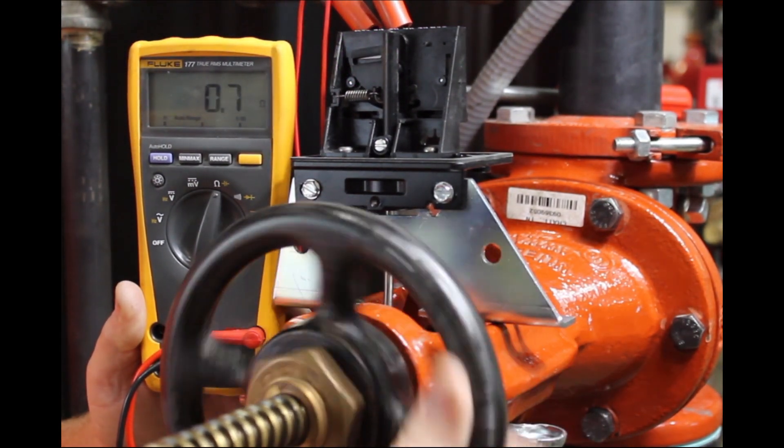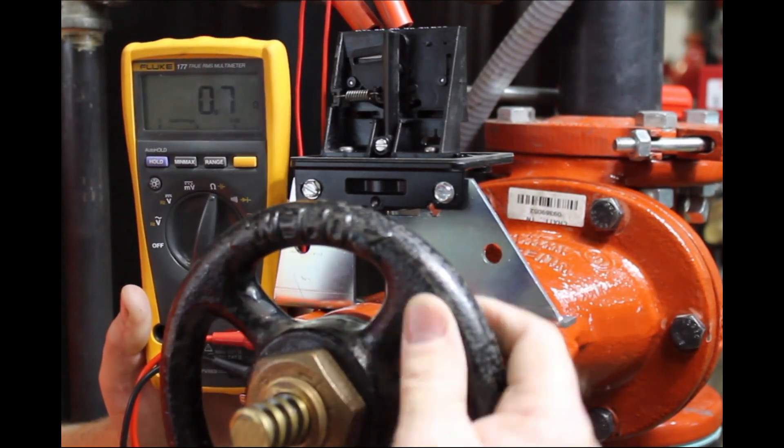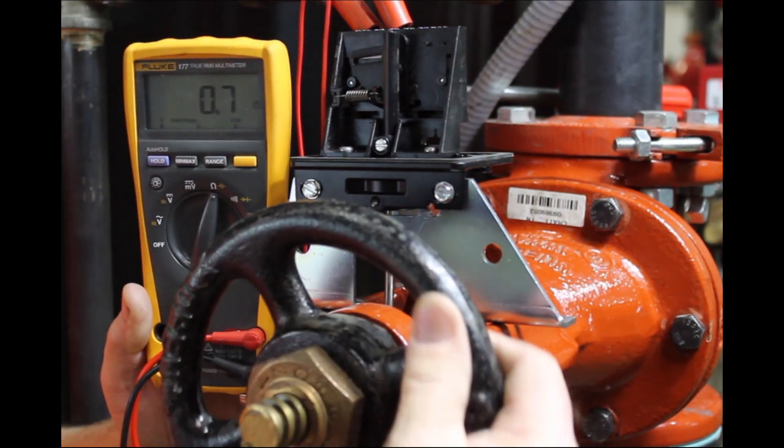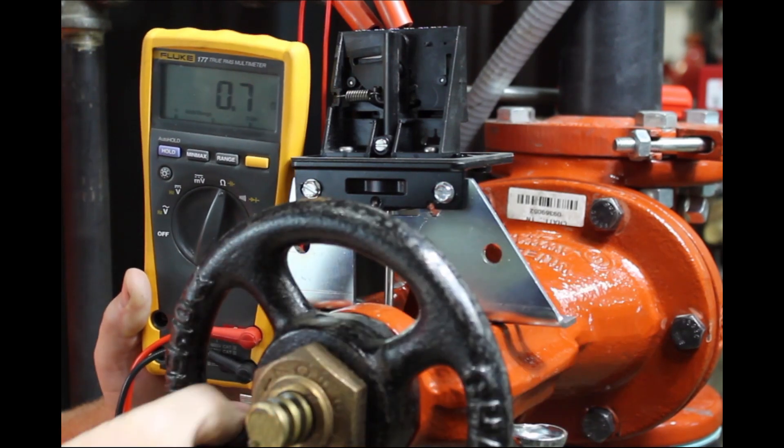It is very important to fully close the valve to make sure the OS&Y does not restore as the trip lever rolls over the threads of the valve stem. Then restore the valve to fully open and make sure the OS&Y restores to normal.